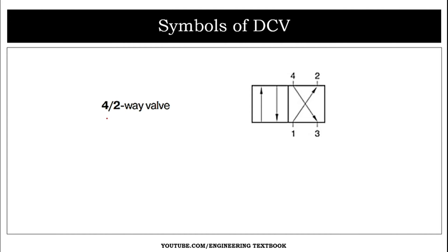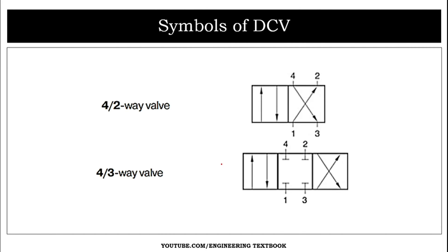Our next symbol is the four by two DCV. Here there are two positions and four ports: one, two, three, and four. Port one represents the pressure port, port three represents the exhaust port, and ports two and four represent the work ports. The next valve is the four by three way valve, which has three positions and four ports, similar to the four by two valve.